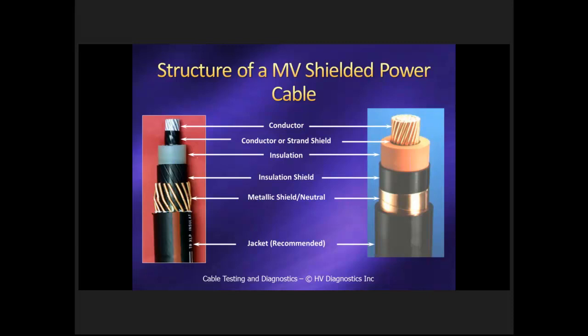But that is covered by a semiconductor shield. And that semiconductor shield is there primarily to take any sharp points away from the conductor and have a very smooth interface to the insulation. The insulation could be anything from on the left, XLPE, to on the right, an EPR type construction. In general, EPR is used mainly in industrial, can be used in distribution as well, and XLPE tends to be, in general, more popular on the distribution side.